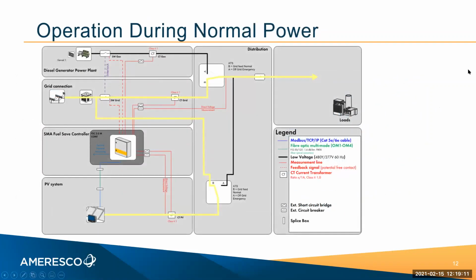So this is a basic single line of the system that is installed here. Starting in the bottom left is the PV system that is currently tied in through an ATS, and I'll discuss why in a second. The yellow highlighted line in this case is during normal operation, so the grid is running and the diesel generator is offline. The yellow shows how the system is connected.